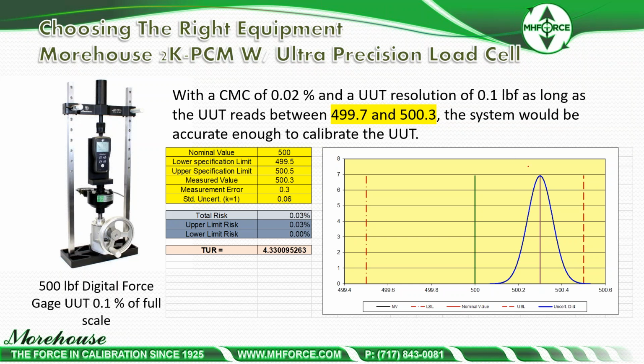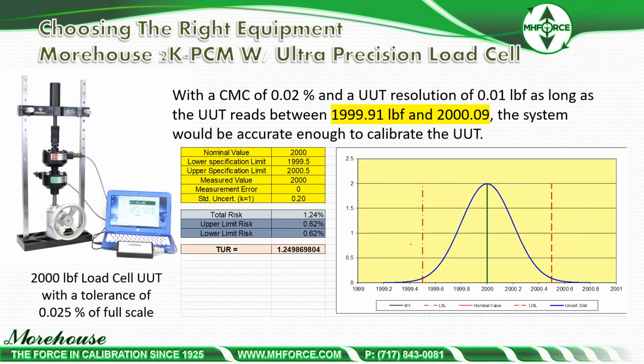This is basically saying, okay, instead of 499.5 to 500.5, I'm going to subtract about 0.2 off of this. So as long as it reads 499.7 to 500.3, you can see down here TUR dropped. I had a much higher TUR on the other one with acceptance limits. Now I have a TUR of 4.33. It's basically saying, hey, my graph here is a little bit wider and I have less room to be in. I'm probably in a normal parking space here where I do have to worry about the door beside me, but not as much. It's a little bit taken away.